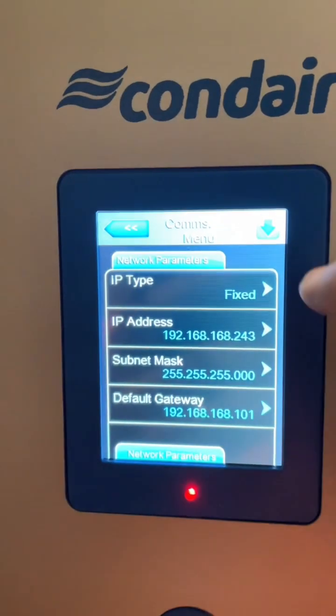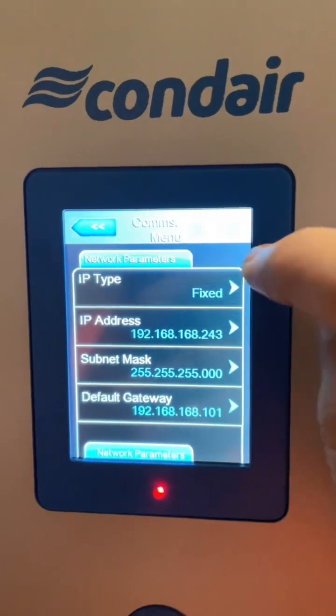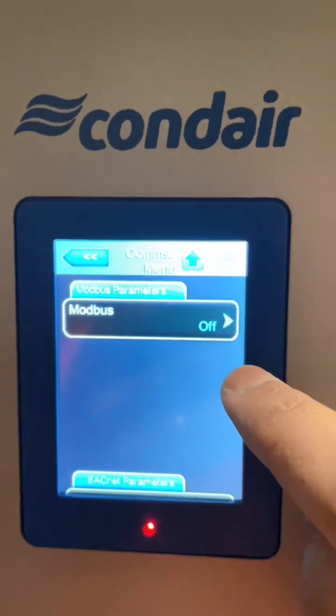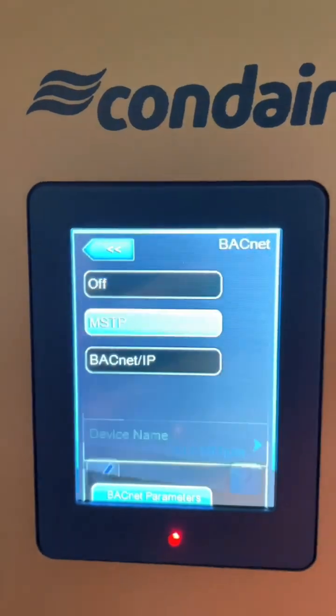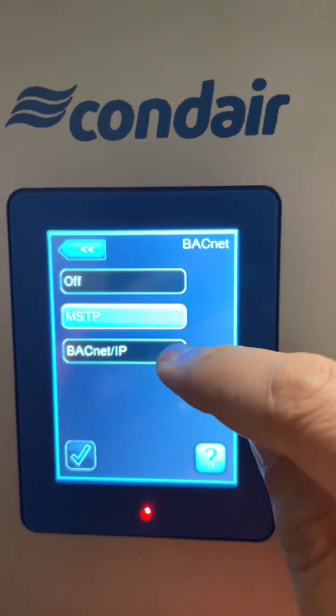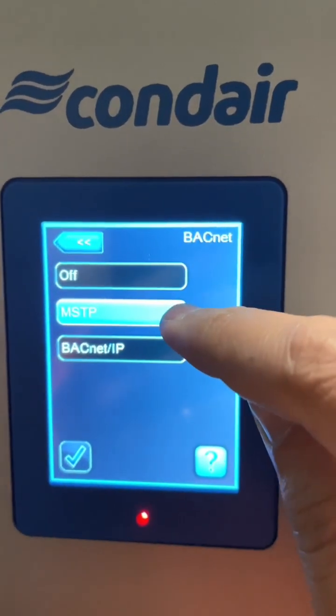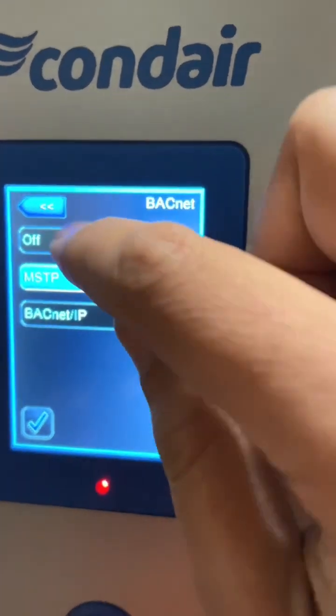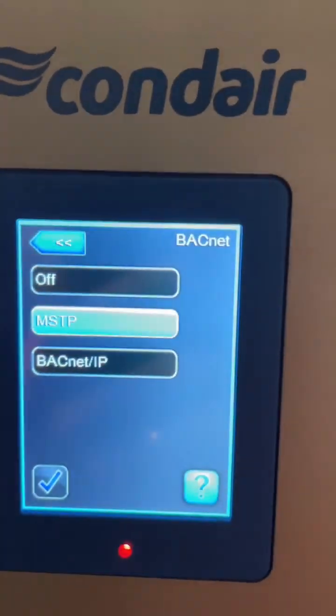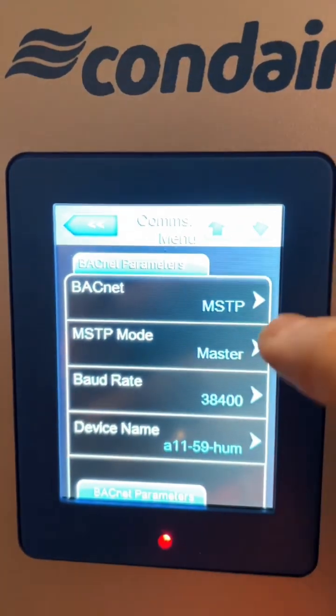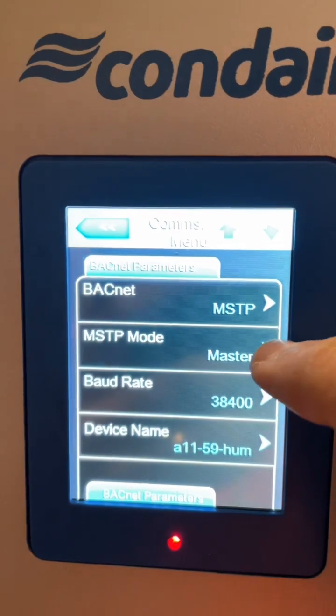Go to communication, you can scroll down and go to BACnet. This will prompt you if you need BACnet IP or BACnet MSTP — it supports both. We are doing MSTP on this one, so you can go back and put it as master.